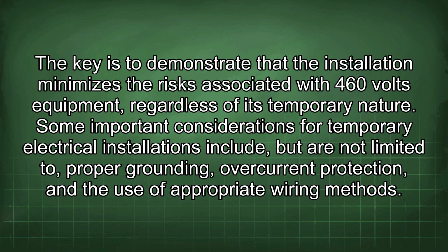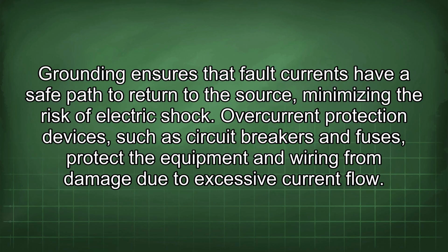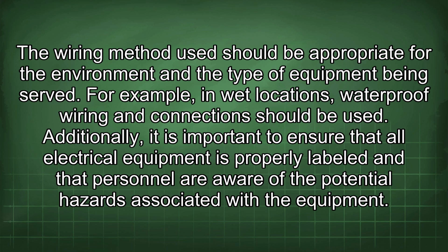The key is to demonstrate that the installation minimizes the risks associated with 460 volts equipment, regardless of its temporary nature. Some important considerations for temporary electrical installations include, but are not limited to, proper grounding, overcurrent protection, and the use of appropriate wiring methods. Grounding ensures that fault currents have a safe path to return to the source, minimizing the risk of electric shock. Overcurrent protection devices, such as circuit breakers and fuses, protect the equipment and wiring from damage due to excessive current flow. The wiring method used should be appropriate for the environment and the type of equipment being served.